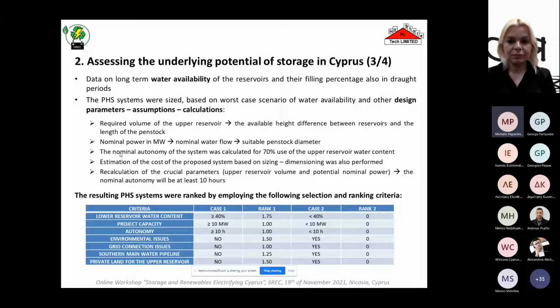So basically, the ultimate question is: if you design a system for, say, 10 megawatts and 10 hours of autonomy, based on your data for water availability during years of drought, would there still be enough water left in the dam to provide that autonomy for your pumped hydro system? Yes, that's the role of this assumption. The critical point is that the nominal autonomy of the system was calculated for 70% use of the upper reservoir, and all simulations were set for drought periods as the worst case scenario. So you ensure that in the lower reservoir there is always enough water, even during droughts.